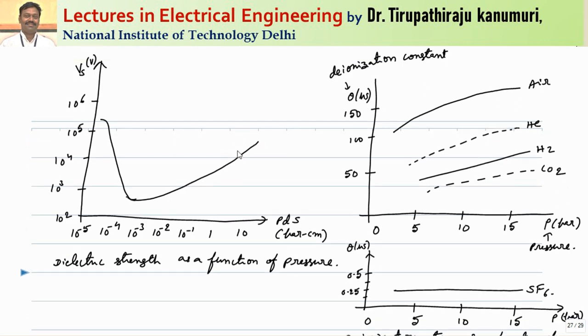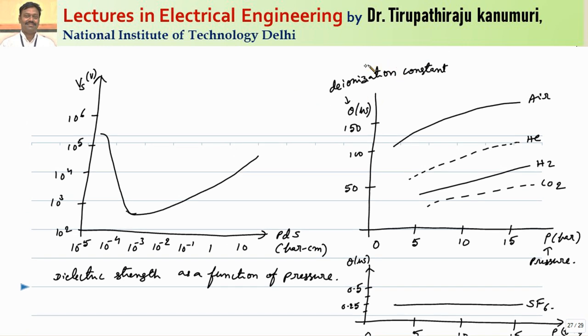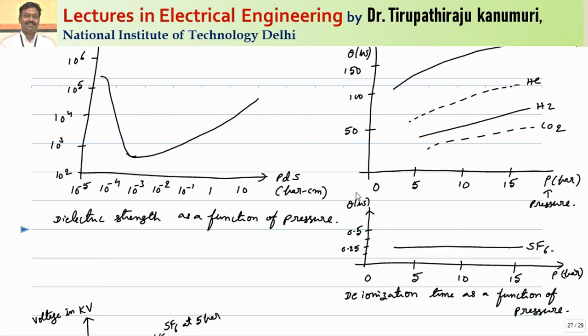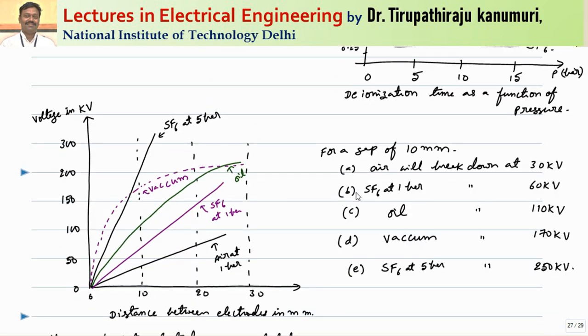Along with increasing the dielectric strength, we also have to deionize the medium. Deionization again depends on the pressure. With the increase in pressure, for different types of gases, the deionization time in microseconds is represented by a curve. Out of all gases, CO₂ has the minimum deionization constant, then hydrogen, then helium, and the highest is normal air. But for SF6, deionization happens in only 0.25 microseconds compared to more than 50 microseconds for other gases. That is why SF6 has the highest applicability.